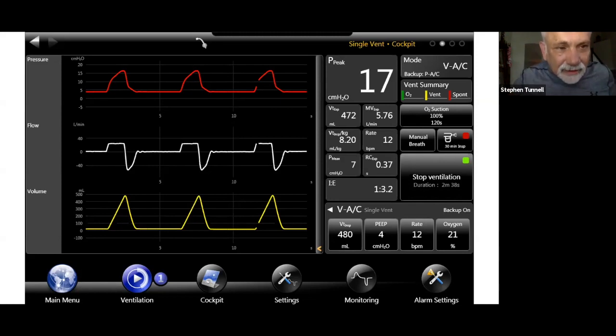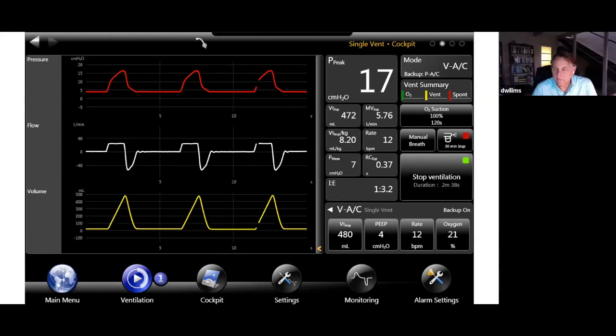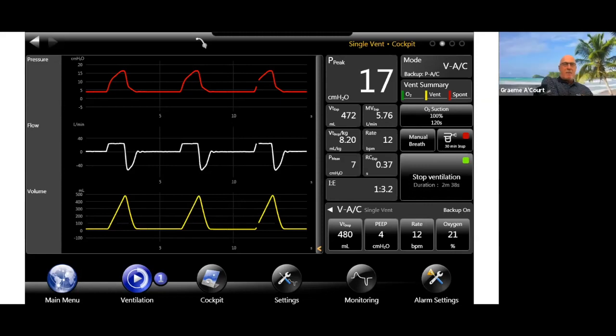But Graeme, I don't know if that's what you were referring to, or if that's the diatribe you wanted me to run off. The point I'm getting at, and I think we've all covered it in some way, is that for example, David, you use the Hamilton, and this is the IMT. What they both have in common is that they both use proximal airway measurements. They use proximal flow sensors, right? So what you're measuring is actually what's happening down there, minus the circuit, minus the humidifier. But you also see a lot more noise because you're closer to the patient.